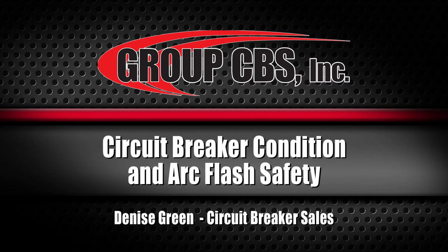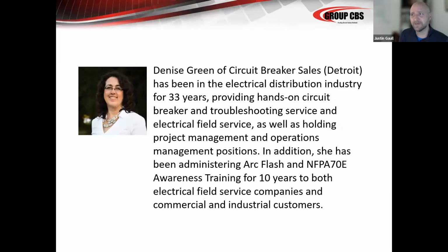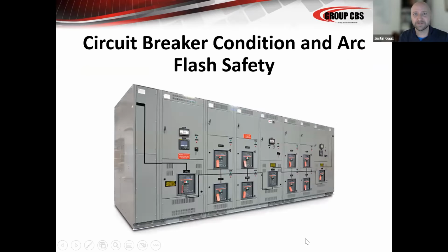We're going to talk a little bit about 1584, and for some, 1584 changes occurred in 2018, so it's kind of older news, but what we're seeing is customers coming to us now saying, hey, we've had changes to our arc flash values based on reviews we've done for 1584 and the new processes. Denise is going to talk about some of those changes you may be seeing since the changes have taken place, and overall circuit breaker condition and how that relates to arc flash safety.